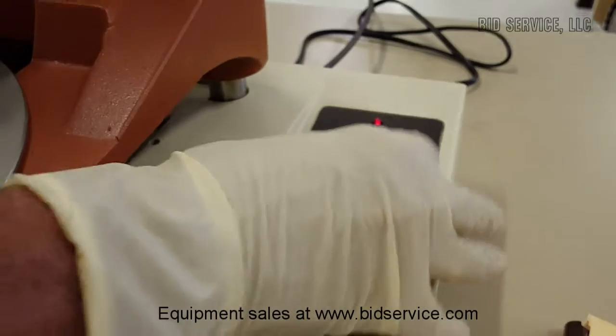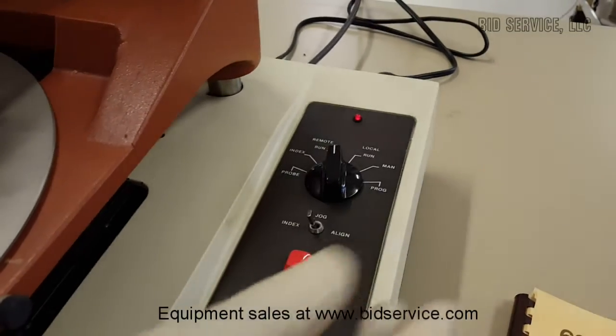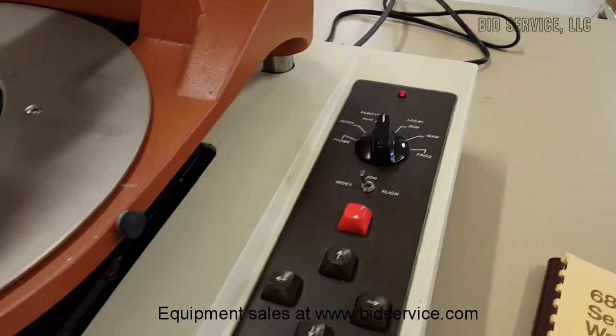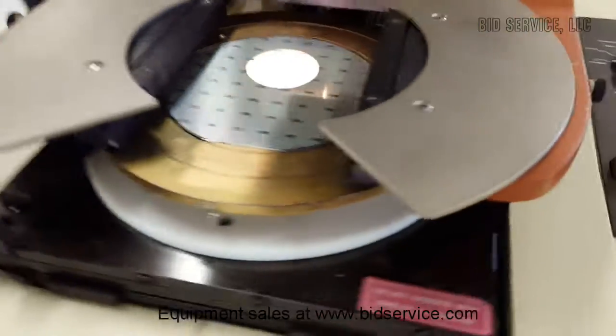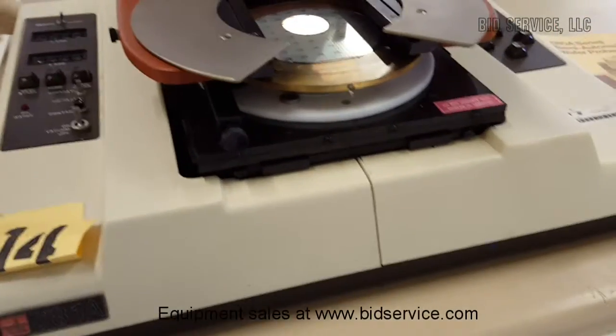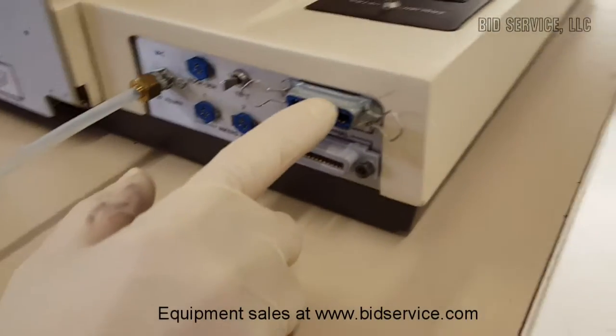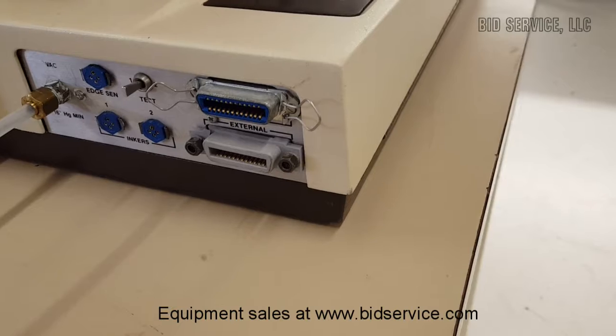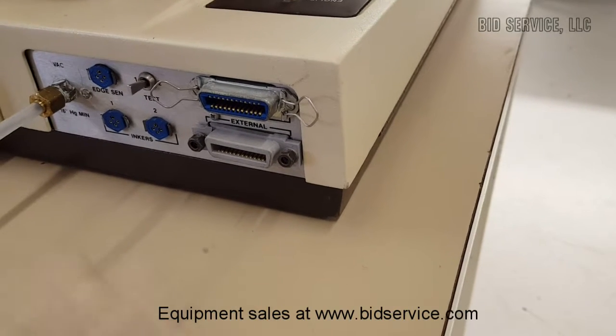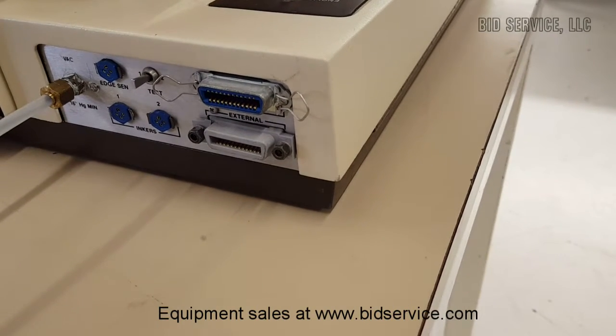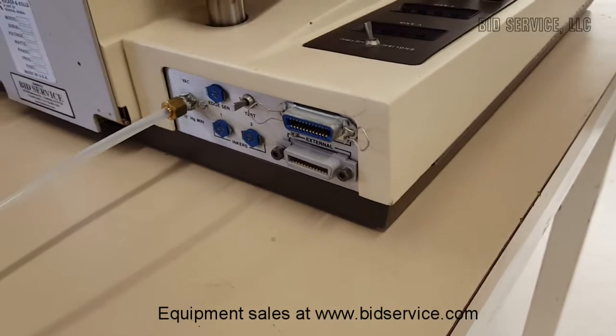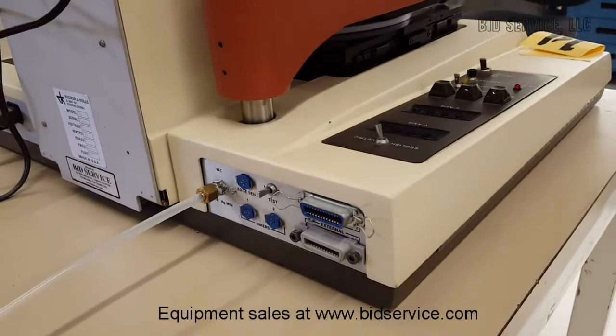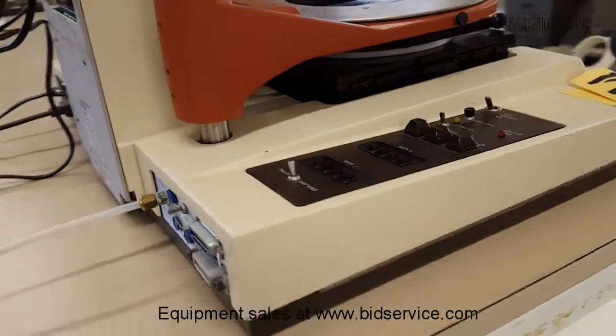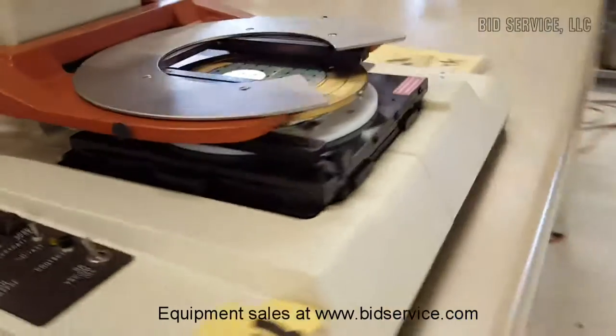I did check out some of these remote functionalities, and let me go ahead and put it to remote run. What I need to do here is jump out, put a jumper between pins 2 and 13 on the tester interface. That'll give me a signal saying that the test is complete, and we can go ahead and run a simulation of how the machine would operate in remote mode without actually testing. Let me get that jumper set up and we'll come back.